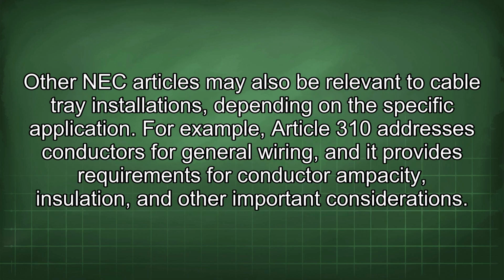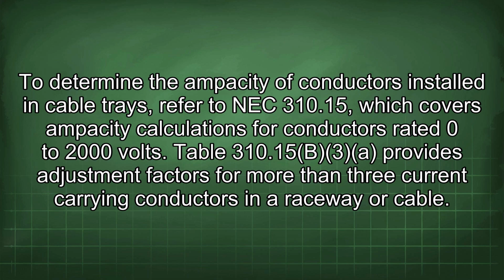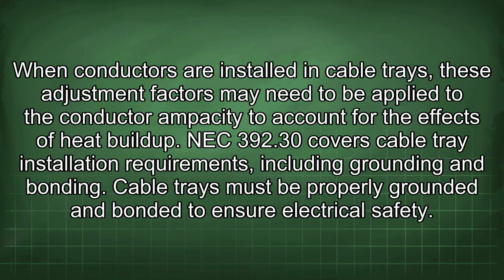Other NEC articles may also be relevant to cable tray installations depending on the specific application. For example, Article 310 addresses conductors for general wiring, and it provides requirements for conductor ampacity, insulation, and other important considerations. To determine the ampacity of conductors installed in cable trays, refer to NEC 310.15, which covers ampacity calculations for conductors rated 0 to 2000 volts. Table 310.15(B)(3) provides adjustment factors for more than 3 current-carrying conductors in a raceway or cable.